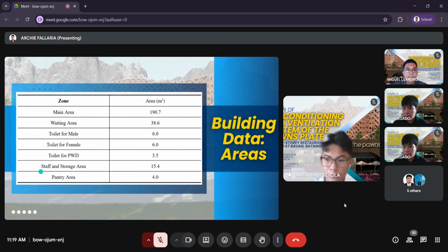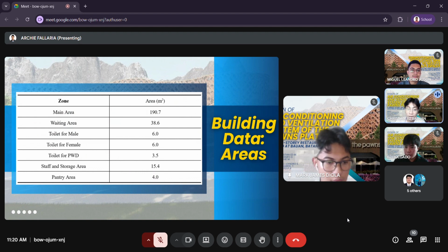And for now, for the building data, specifically for the areas, the facility is divided into various functional zones, each allocated with specific area measurements and corresponding ventilation and air conditioning requirements. First, the main area, which has an area of 190.7 square meters, and the waiting area with an area of 38.6 square meters, are designated to be air conditioned using a fan coil unit or FCU, ensuring occupant comfort in these high traffic spaces.